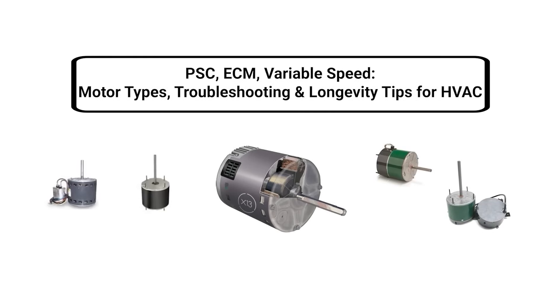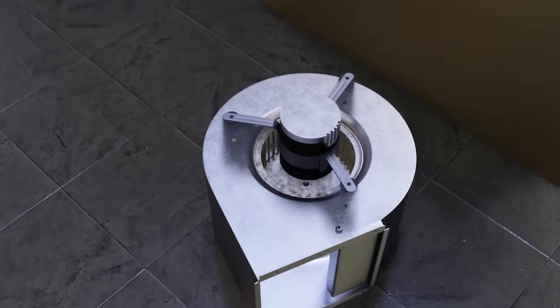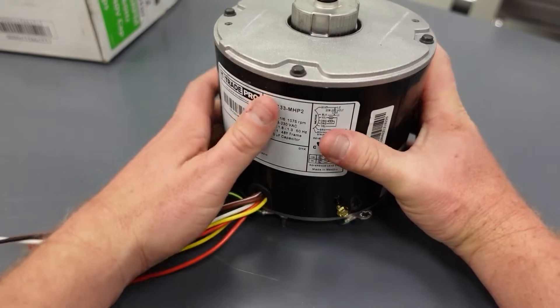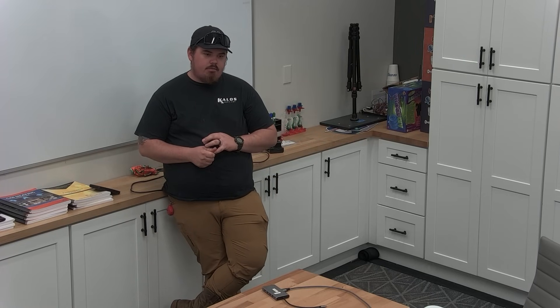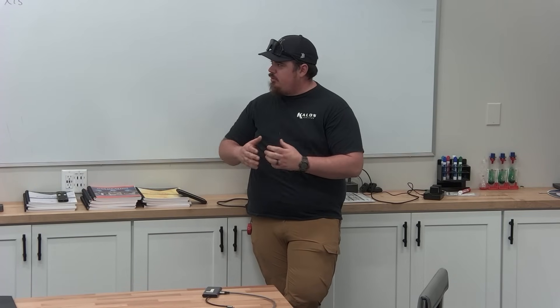I wanted to cover types of motors — blower and condenser fan motors — so understand the market that we're in. Our design CFM is 350, and we're in a high humidity market in the south. So what we need to do is not only control the temperature, but also control the latent load, which is the humidity. We're dropping our blower speeds down; most of them come on speed tap 3, and we're dropping down to 2, sometimes even 1, depending on tonnage size and application.